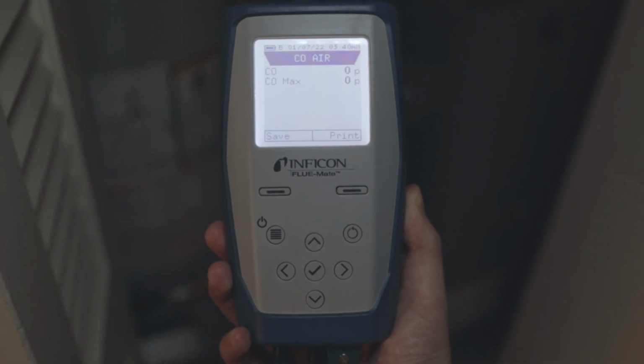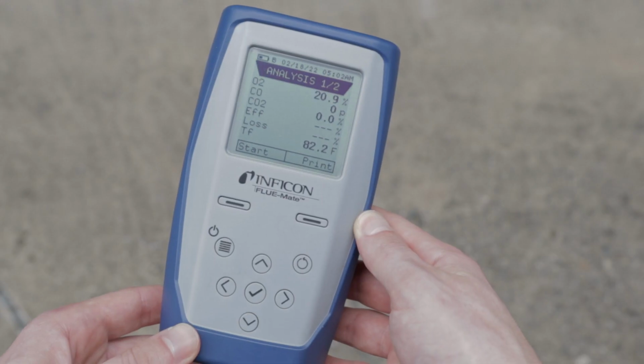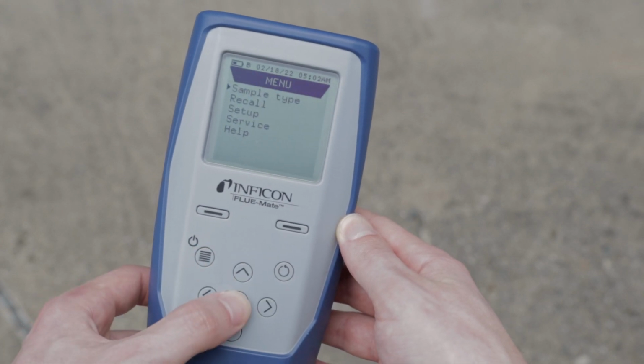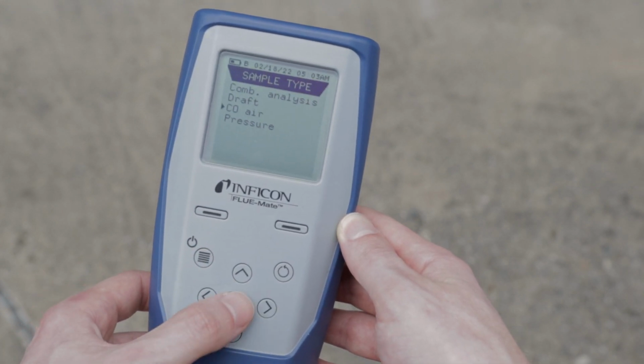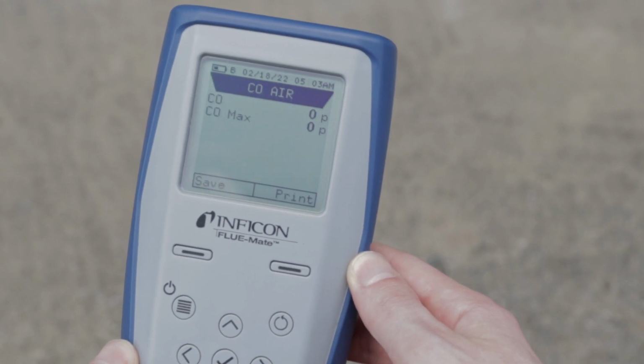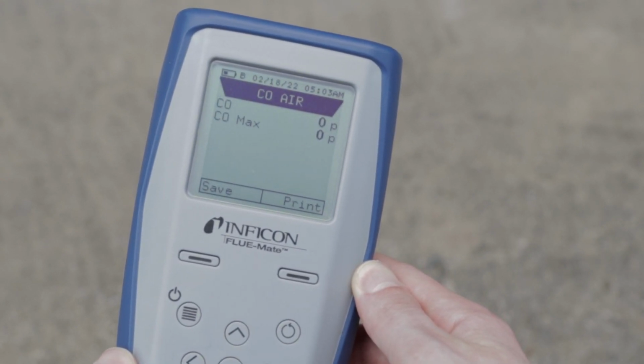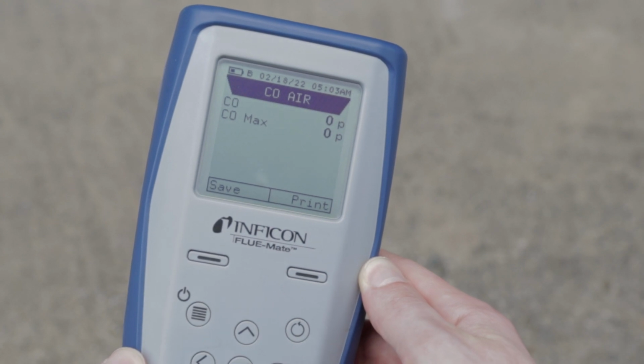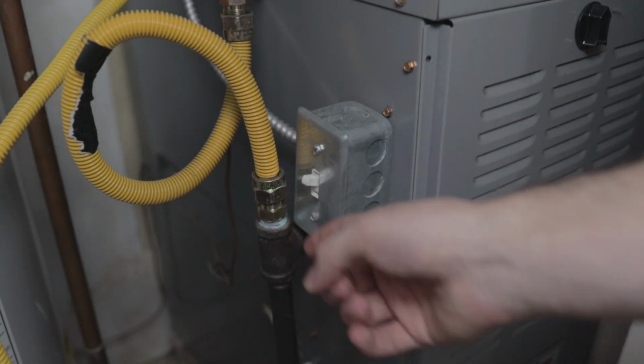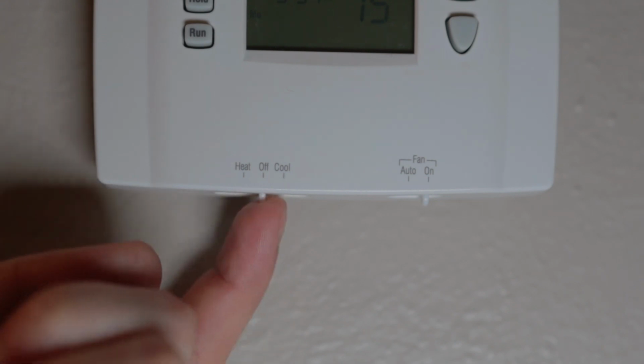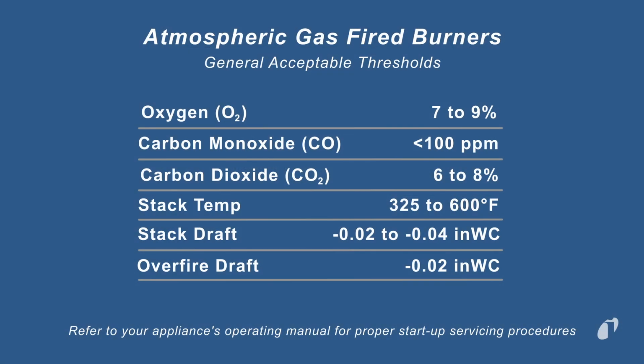Next, ensure your indoor work environment is safe by checking the ambient CO level. In the menu screen, select Sample Type, and then CO Air. Monitor the CO level as you walk around indoors. You can save or print the results of the ambient CO analysis if you wish. Turn the heating system on and let it go through its startup process before testing combustion. The operating manual for the appliance should list the acceptable thresholds for draft, excess air, carbon monoxide, stack temperature, and other relevant parameters. Have these handy during combustion analysis.